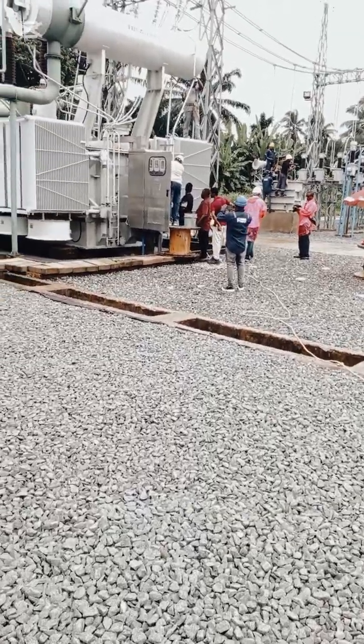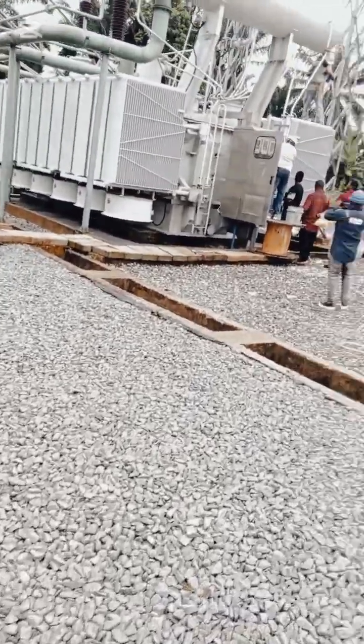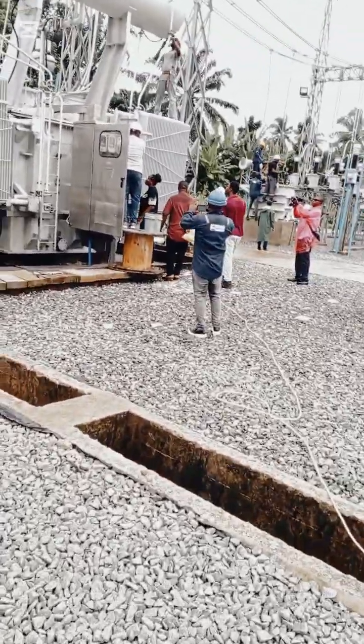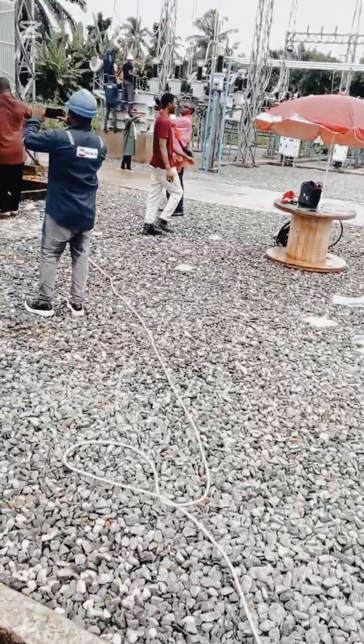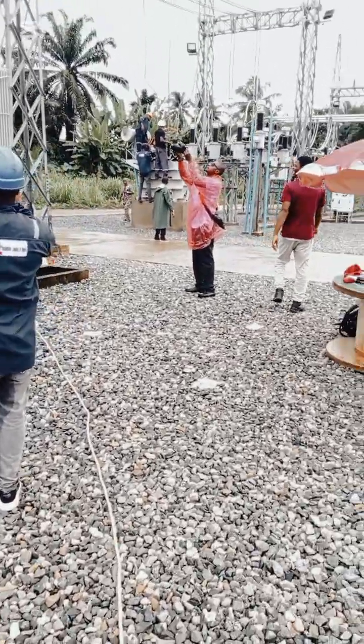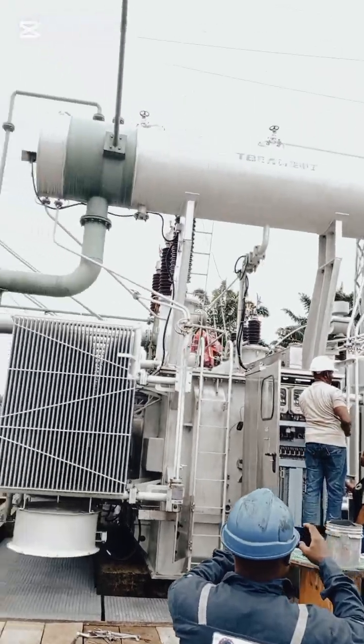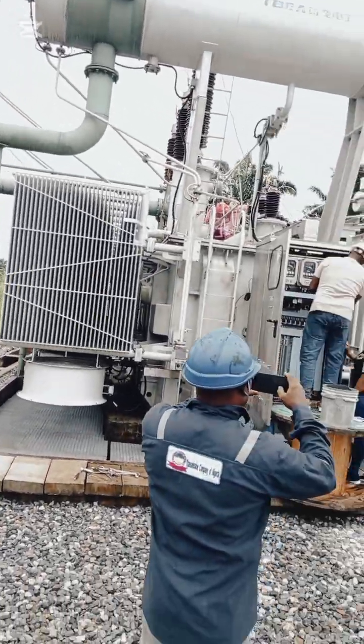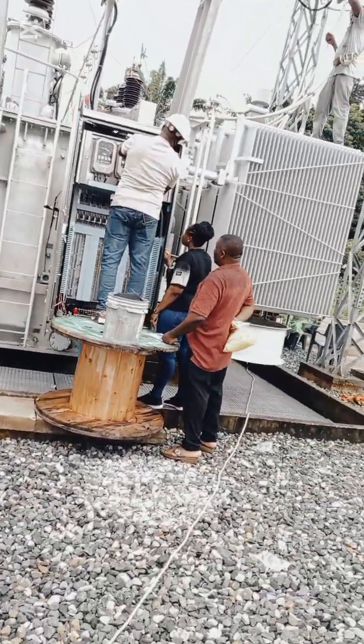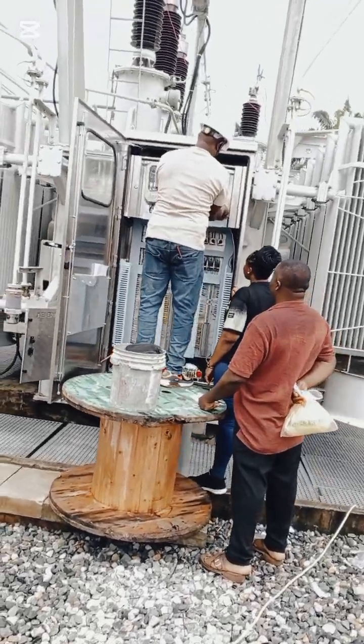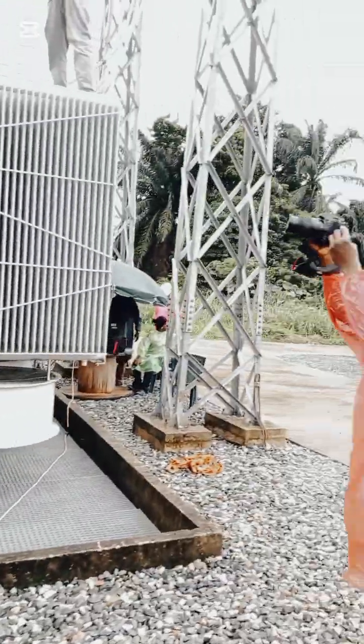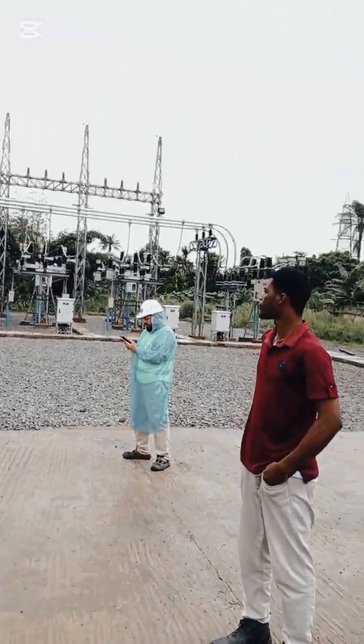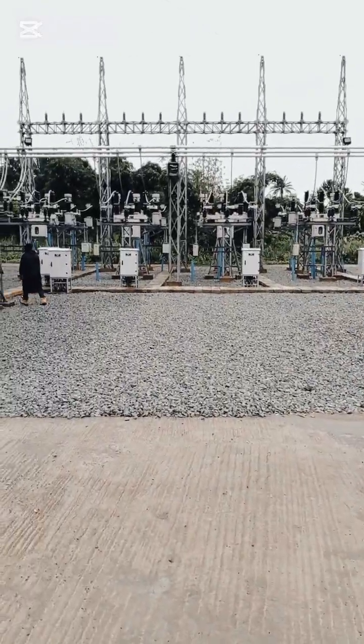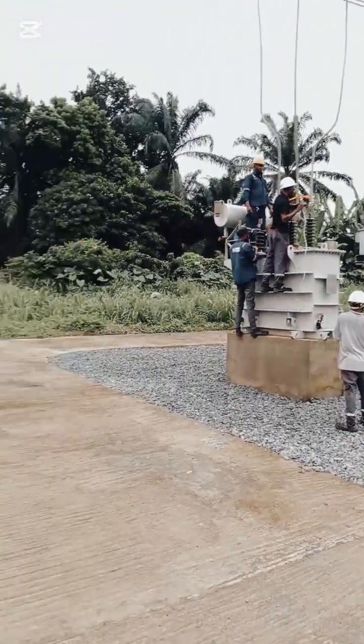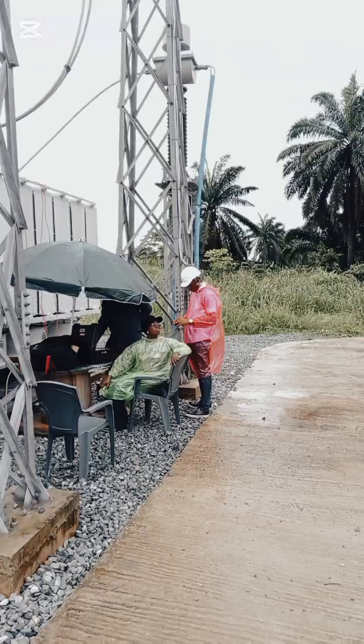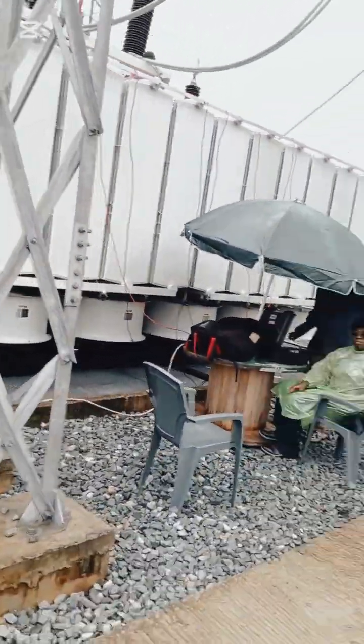Part 2: essential electrical tests. After oil filling and settling, these tests are paramount for assessing the electrical integrity of the transformer. 1. Insulation resistance test, or Megger test. Measures the integrity of the insulation between windings and ground, and if applicable, between the core and ground. Why it's important: detects gross insulation breakdown, severe moisture ingress, or contamination. It's a quick check for major problems.